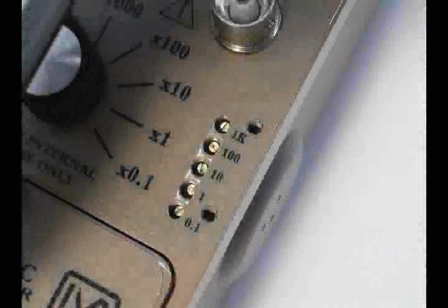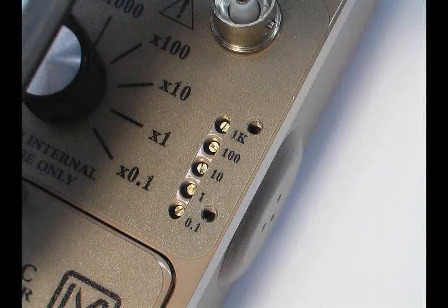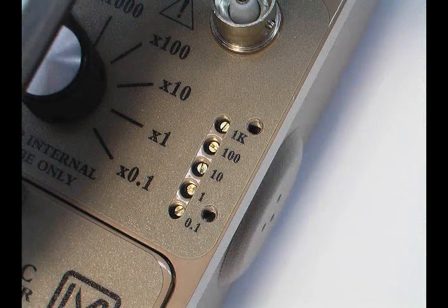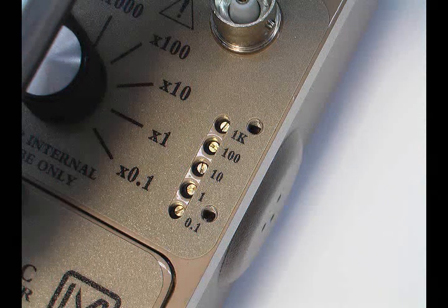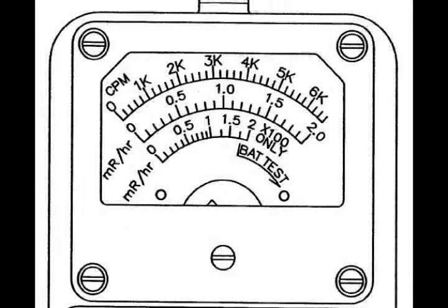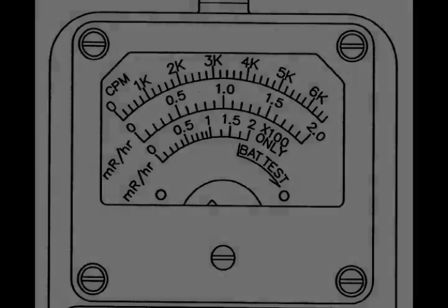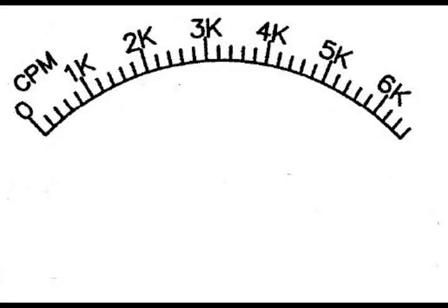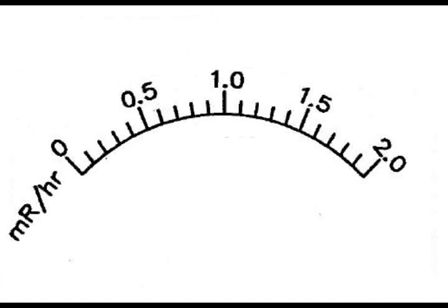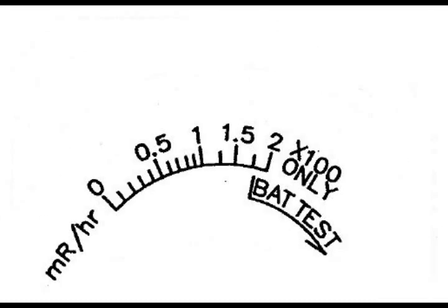The calibration controls have a protective cover to prevent tampering. They are recessed potentiometers which are used to calibrate the individual range selections and allow for high voltage adjustments from 400 to 1500 volts. To read the meter face dial, multiply the meter reading by the range multiplier setting. The dial on this Model 14C-RK has 3 arcs to show count rate or exposure rate: a CPM or counts per minute scale, a linear milliR per hour scale, and a nonlinear milliR per hour scale.